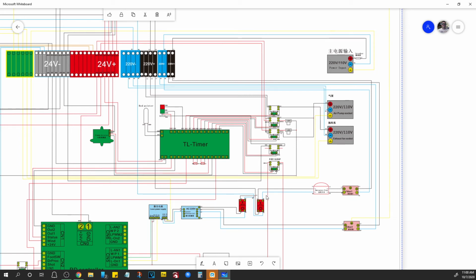If you're still not getting power, and you are confident that you can use a digital voltmeter, you should plug the machine back in and do a few spot checks to make sure that you're getting 110 into the machine. You can check it at the connector on the back side or on the front side, or you can just go to these screw terminals here, and they're labeled and they'll tell you which ones they are, and you can check for power here. If you get it here, you know that your power cord and all that stuff is okay. So then check it on this side, and if you get it here, you know that you're good.